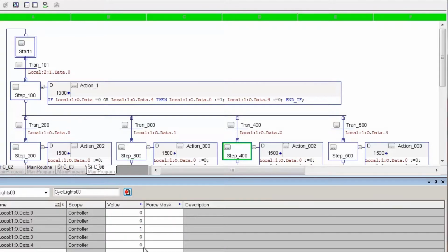Now if we were using Ethernet instead of RS-232, if we were using 100 meg, I mean seriously, 100 meg versus 38.4K. However, like I said, my Ethernet interface card is tied up doing something else. I don't want to interrupt it. This will be good encouragement not to use RS-232 unless you have to. I typically consider RS-232 the back door into the Logix engine.